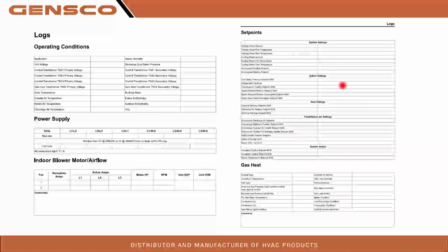What's your set points? Indoor motor airflow, right? So we can change our airflow on these. It's good to notarize what your actual amps, your horsepower, RPM, and what's your external static pressure. We've had a couple of them where we went back out, and our static pressure was off. They just set the unit like for like on the roof, and the ductwork, I don't know if they did a TI in there and took off one of the returns, but we had over 1.5 inches of water column, and that thing was not going to work like that. So they had to add a return afterwards.